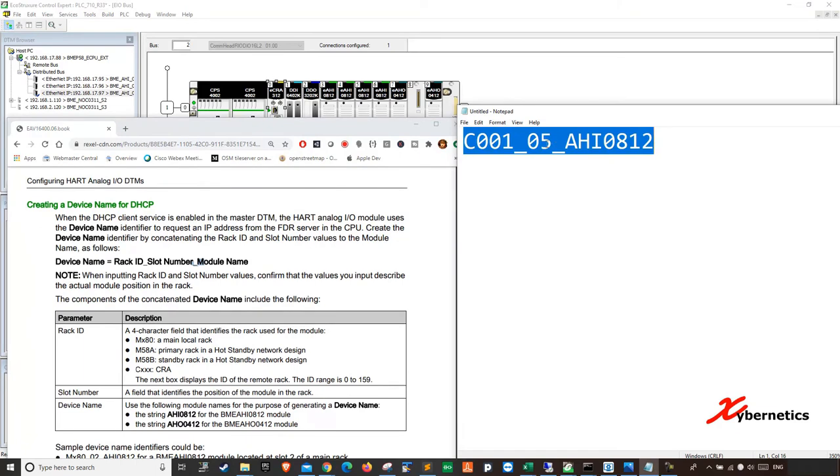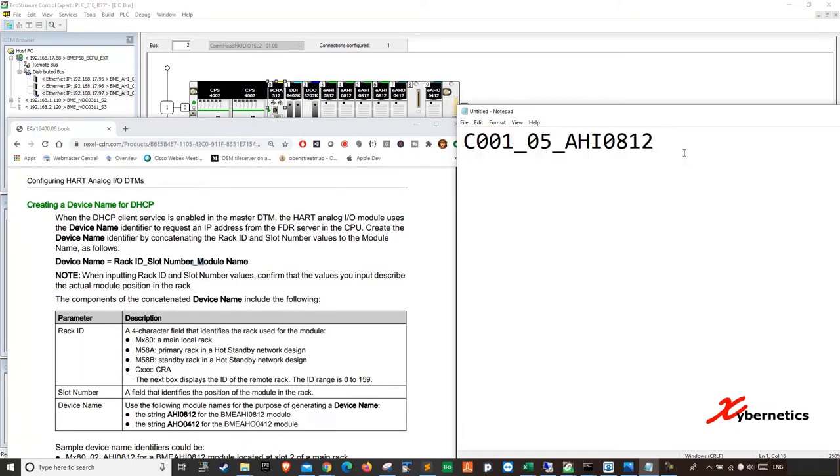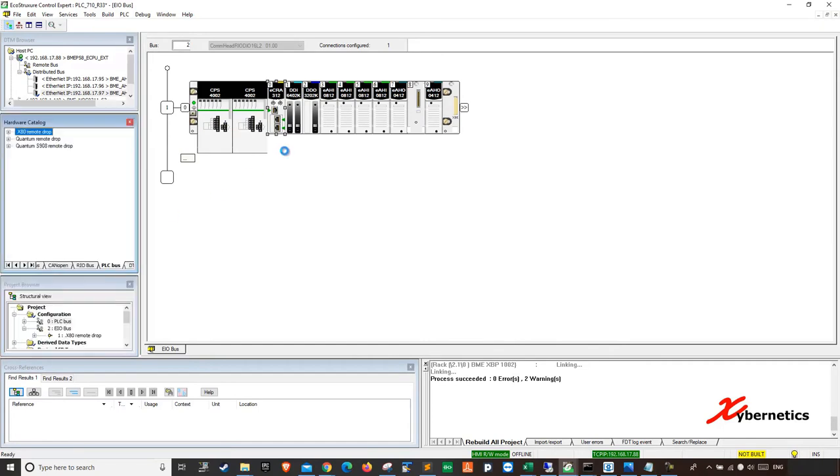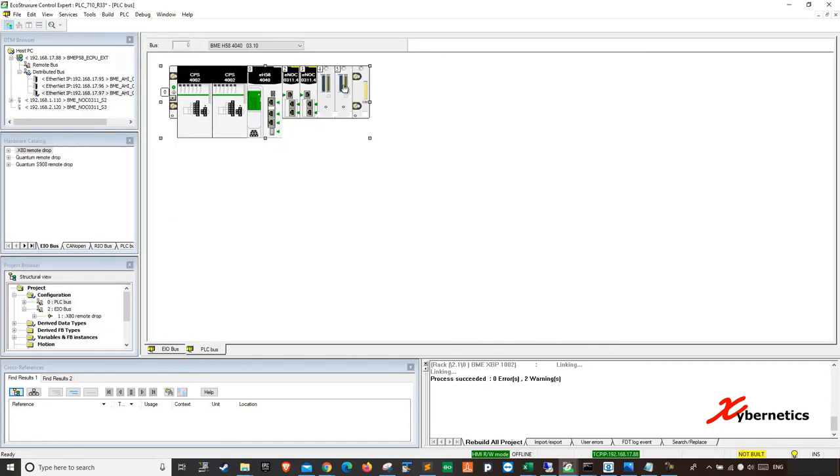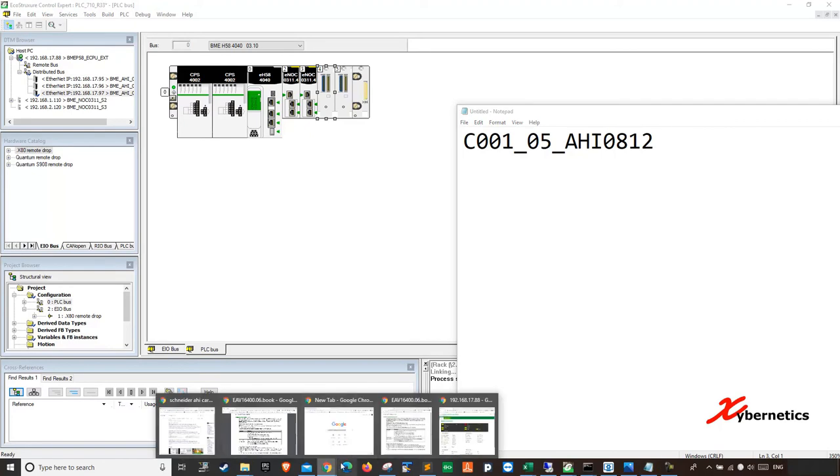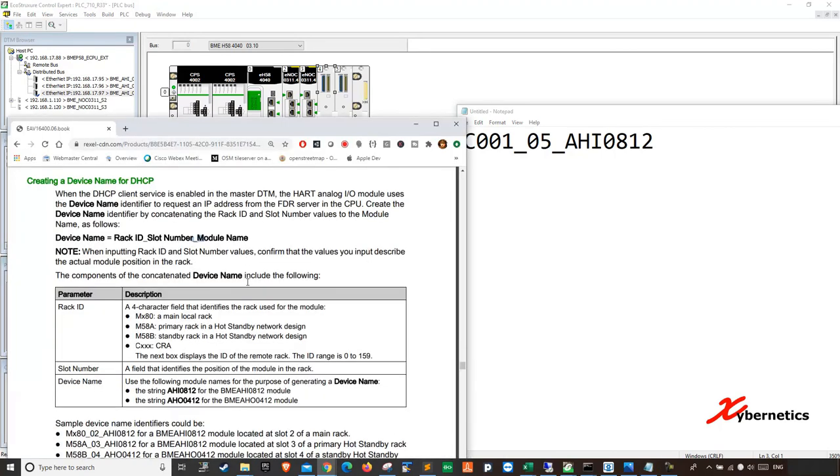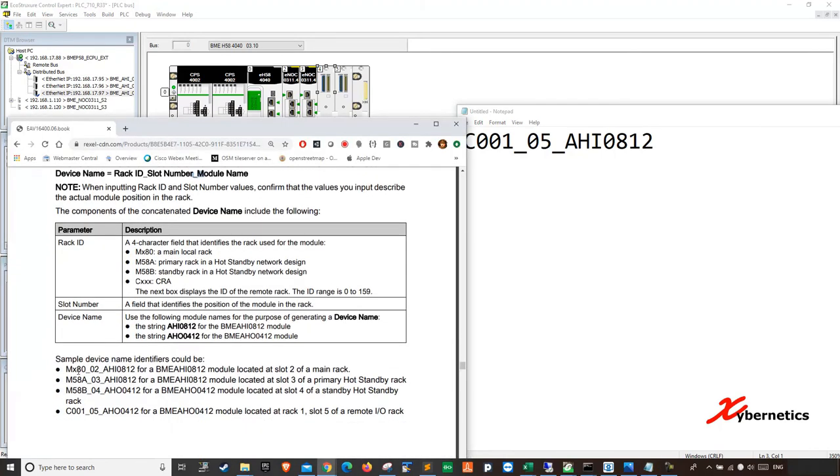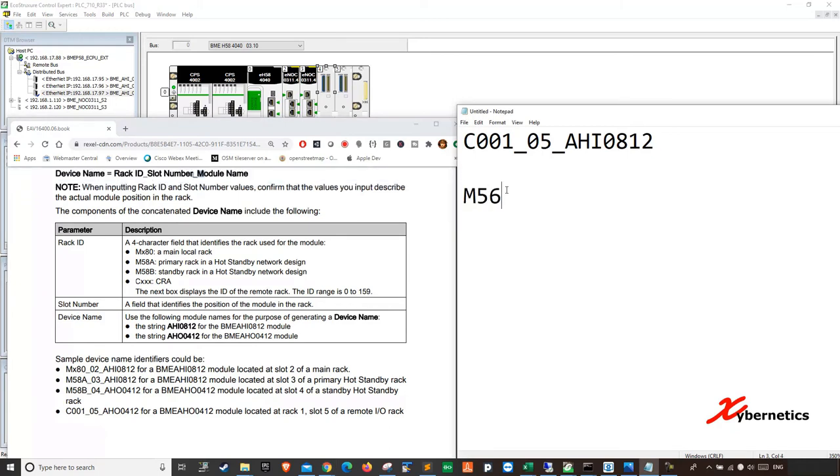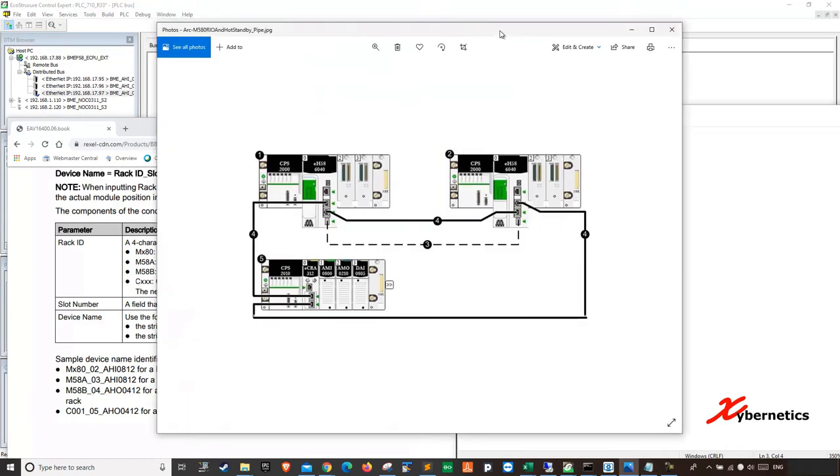Before I do another example, let me show you. So let's say if your AHI is on your main CPU bus itself. So if you double click this, if you do have your AHI on say slot 4, what does the identifier name look like? So it's going to be, this is 580. So it's going to be M580. If it's on the hot standby, one of them has to be identified as A and the other one has to be identified as B. I have a video on how to actually set that up here. I'll put in the link below here on this video.